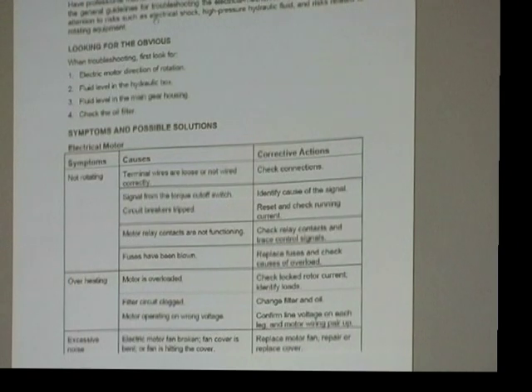Okay, so on torque shutdown, we will have SCADA, basically that motor's going to come up too, right? Yeah, the motor will. We'll have it where SCADA will not allow it to just automatically start. I mean, if it's pushing against it and it shuts down and then it kind of unwinds itself, there's a lot of energy in the arms. I don't want it to keep butting against something and then start, stop, start, stop. I don't want it that way. It should stop and stay stopped until someone investigates why it stopped. Yeah, because they can restart it from SCADA, but they've got to go out there and find out what the problem is, and there would be an alarm. Okay. Right. Make sure it's in SCADA that way.